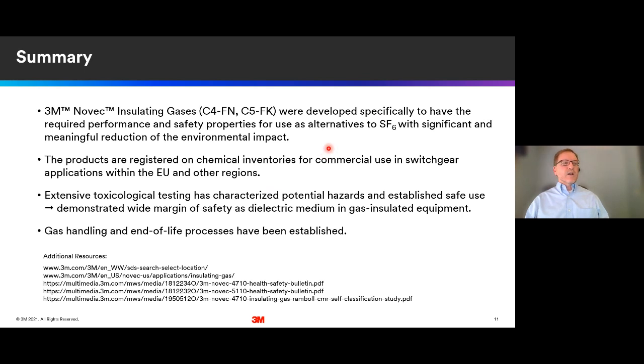The products are registered now on the chemical inventories around the world. And that's as a result of the extensive toxicological testing that's taken place that identified what potential hazards there could be and established safe use for the materials. And as I showed, compared to expected exposures to insulating gases, there's a very wide margin of safety. And then finally, gas handling equipment has been established, not only for preparing mixtures and initially installing them, but also for recovering them at the end of life of the equipment.